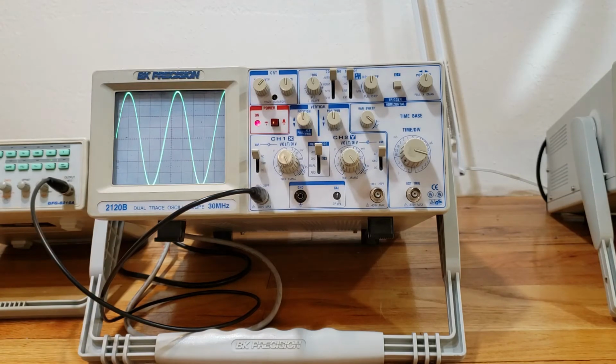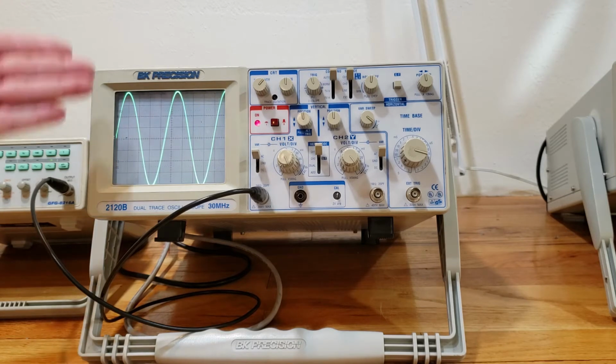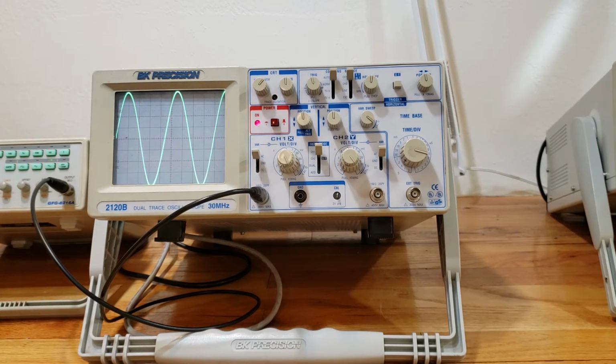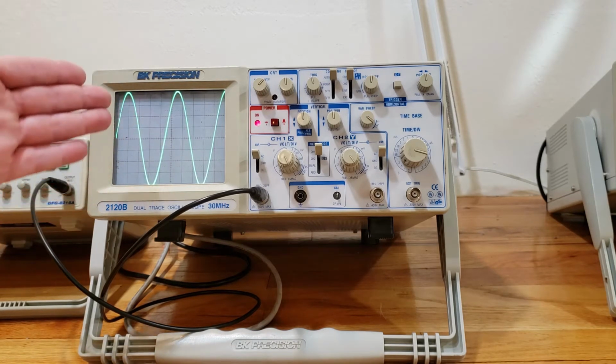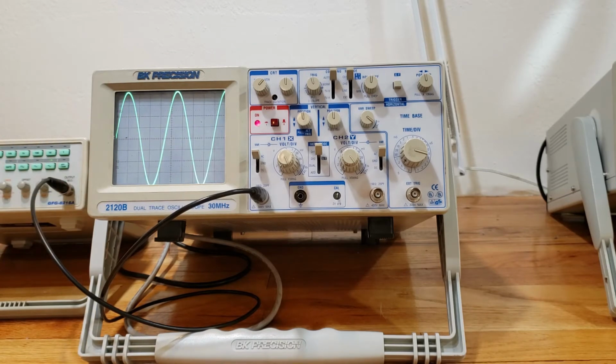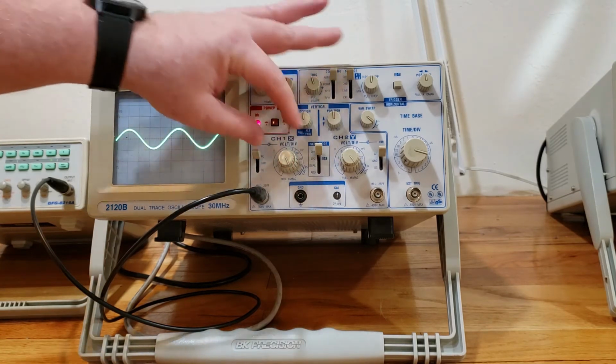So if I were to try and take a voltage measurement, of course I can't get it all on the screen there, but whatever voltage I came up with would appear to be 5 times greater than it actually is. Understanding that, I would then divide by 5 and that would give me the correct voltage. The purpose for that is if I have a really small voltage signal, I can amplify it 5 times and that would help make it larger for me to take a measurement. Then I would divide by 5 and come up with the correct voltage measurement.